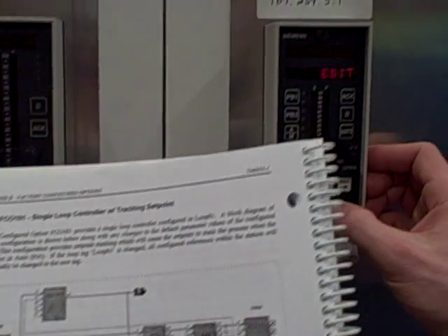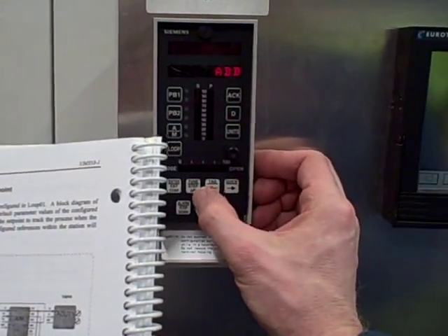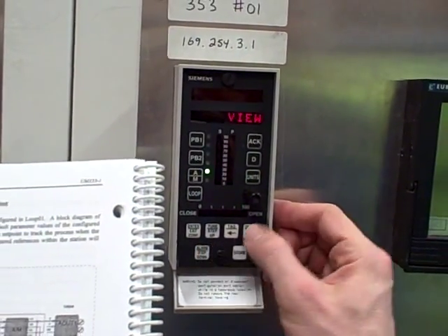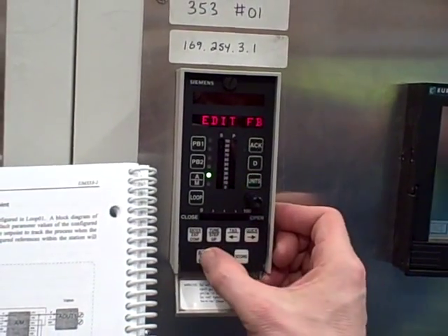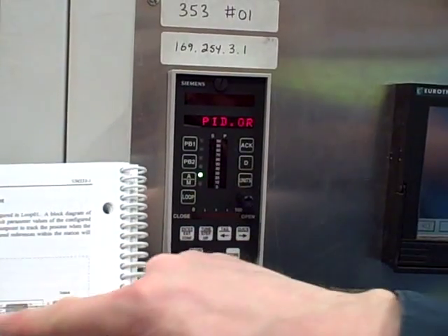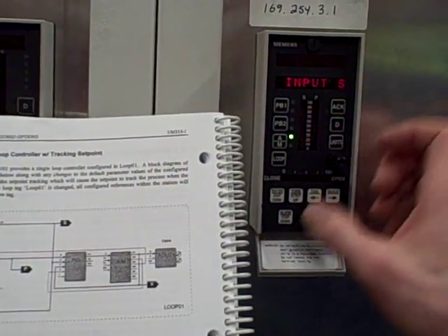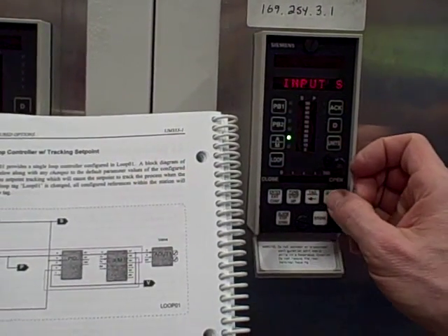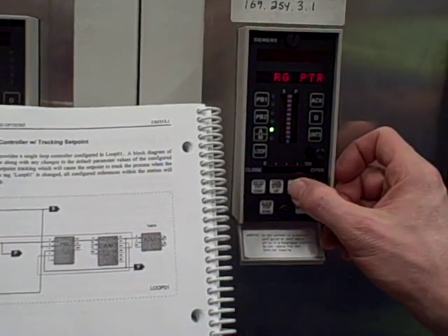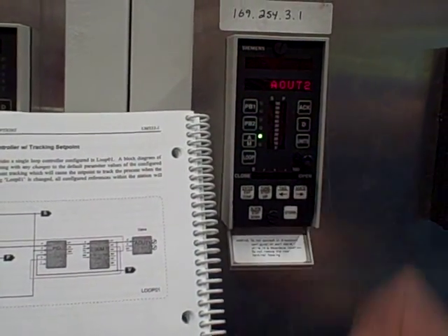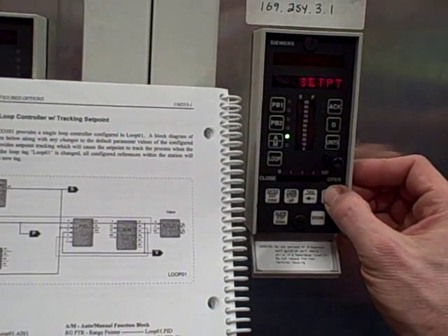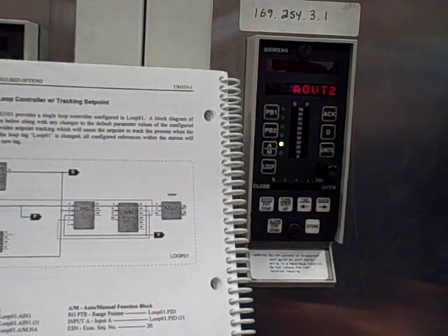Stepping up, going to edit — actually, let's go out of this entirely, I hit a wrong button. Let's do the configuration again. Stepping down twice, we're going to 'edit function block.' We can take a look at our original analog output block right here — it's got a range pointer that comes from PID dot OR, and an input S which comes from auto manual block 01. Now I'm going to step up and select analog output 2. Notice how that now shows up as one of our options. Looking at all the available blocks in this function program, I can see that analog output 1 and 2 are both there — it didn't used to be there, but I've now added it.